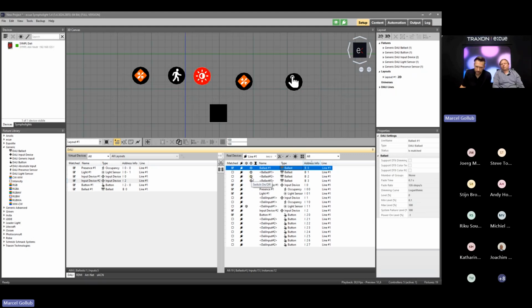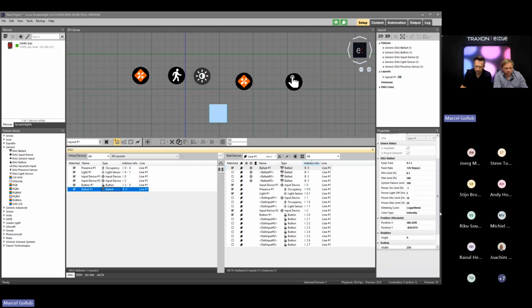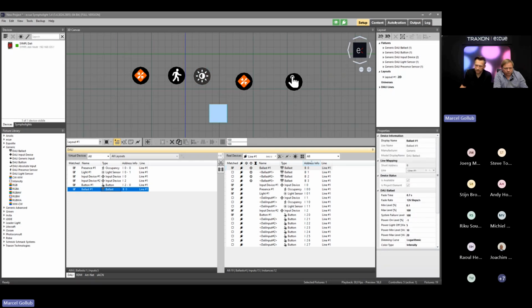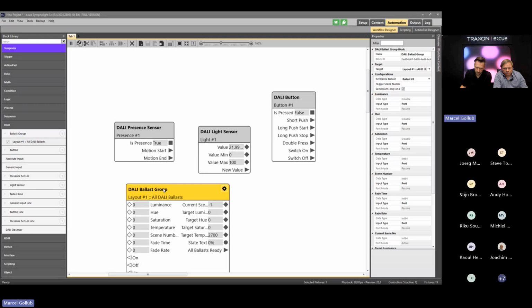With Sympholight, you also have this direct testing functionality, so you see the response directly in the 3D view. Really straightforward. You can also configure some thresholds, and you see some further settings on the right side. Besides this, in the automation, you can control it via the ballast group. If you send a value of 0%, the relays are open, and above 90%, the relays are closed.